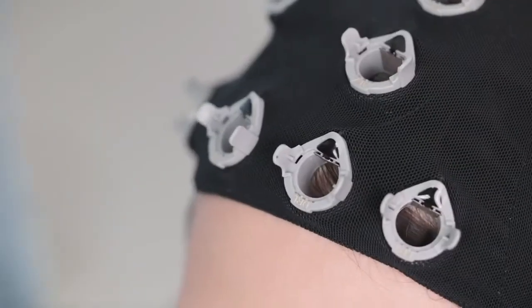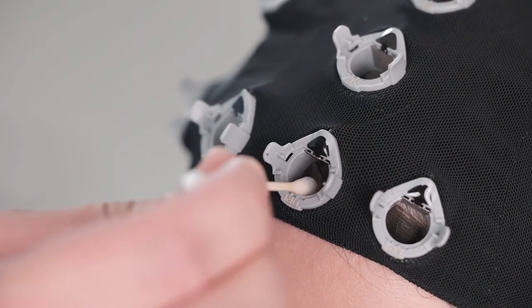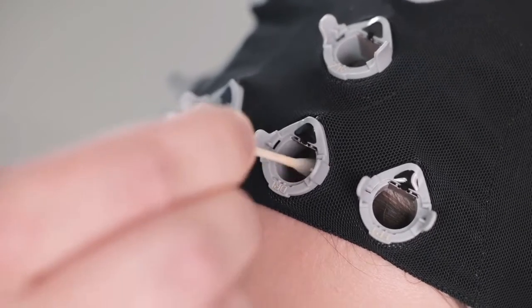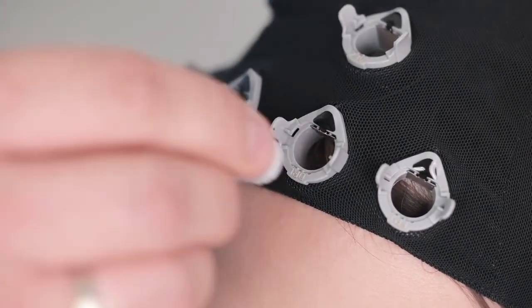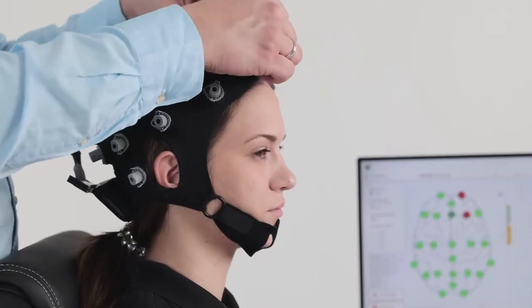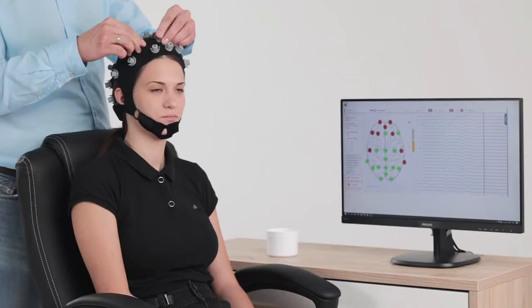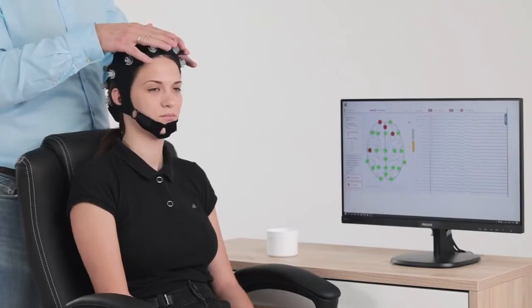Additionally, you can use the cotton swab, previously wetted in the saline, to split the hair so the electrode sponge can have better contact with the scalp. Repeat the process until the desired impedance values are reached on all electrode sites.